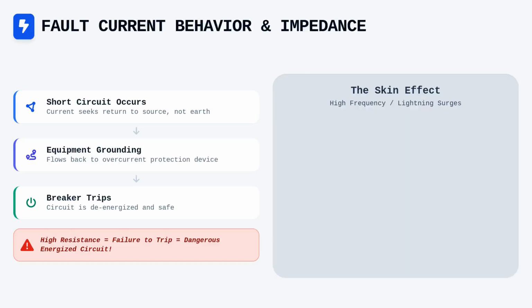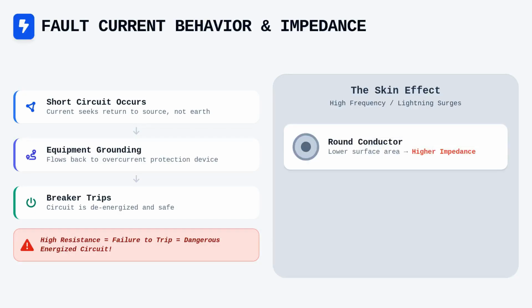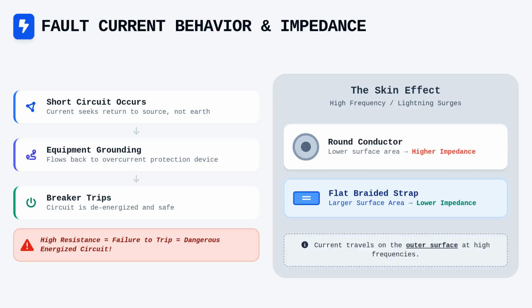This is where the physical characteristics of conductors come into play, specifically concerning the skin effect. At high frequencies, such as those found in lightning strikes, current tends to travel along the outer surface of a conductor rather than its core. Consequently, flat braided straps are often superior to round conductors in these scenarios because they offer a larger surface area relative to their cross-section, effectively lowering the impedance for transient surges.